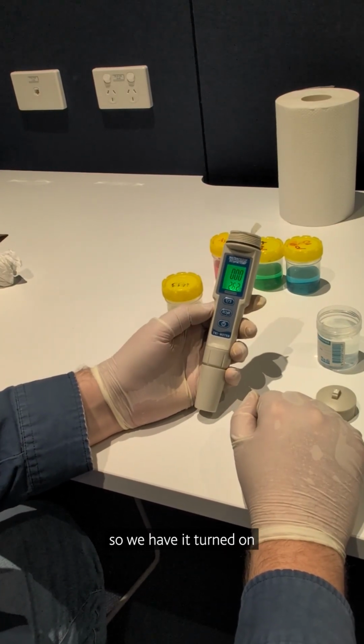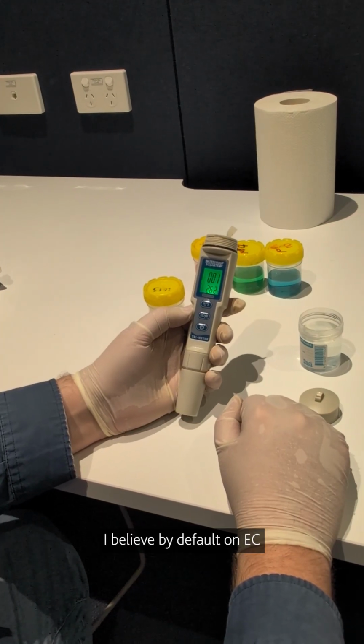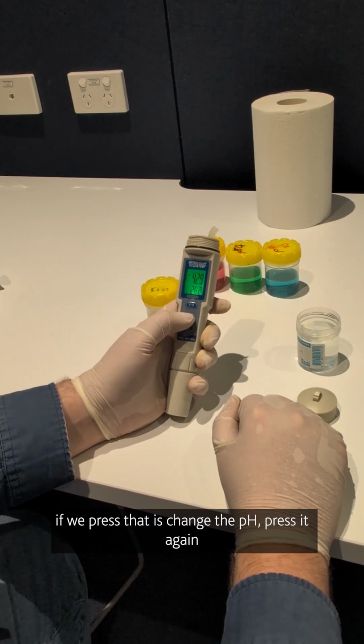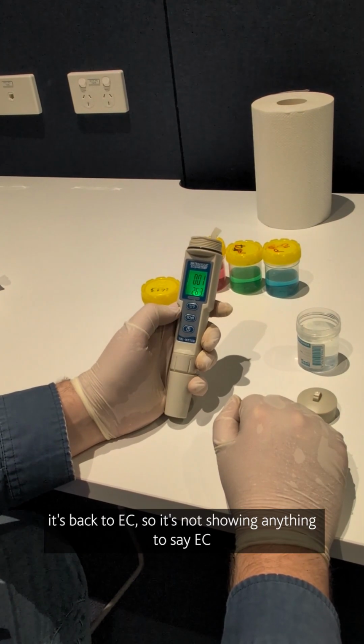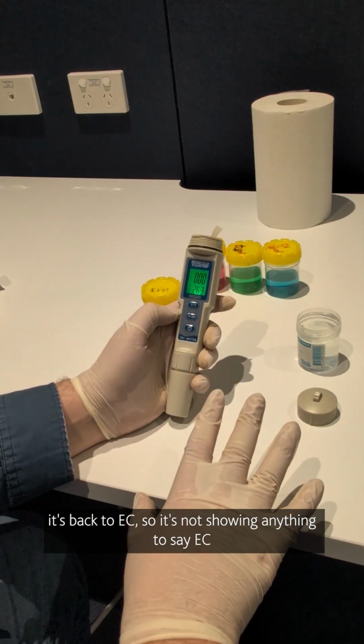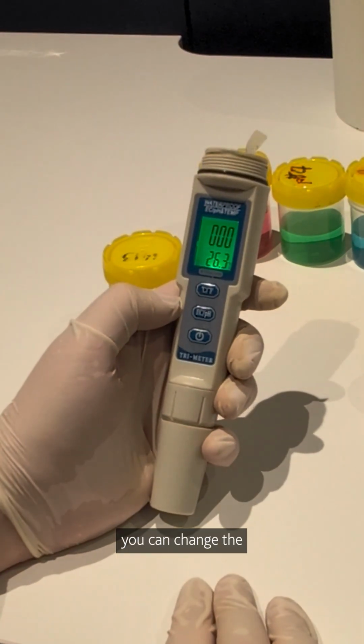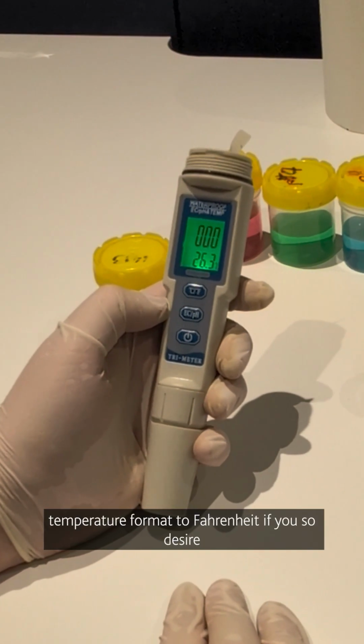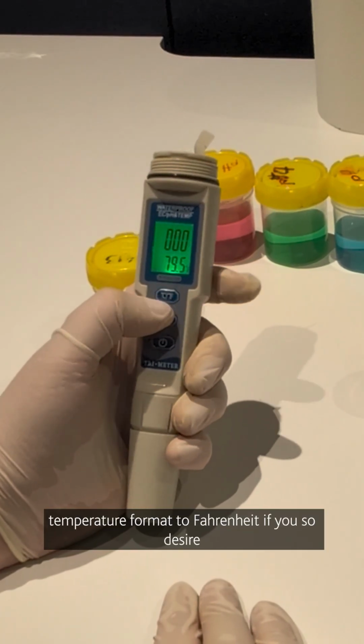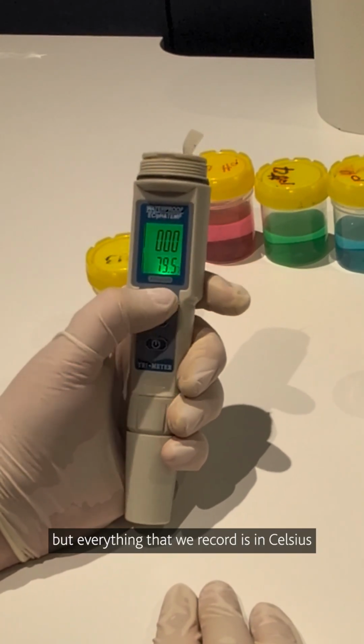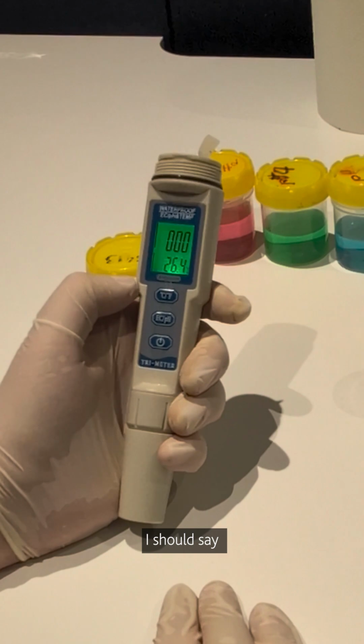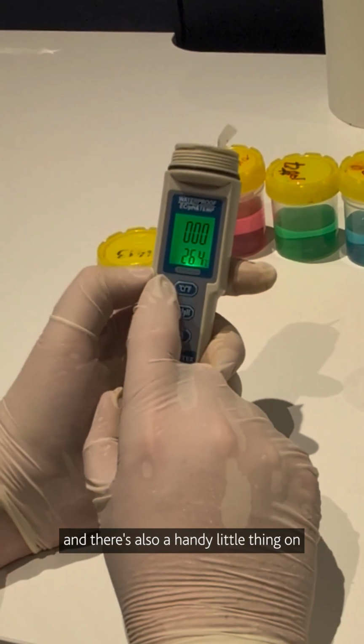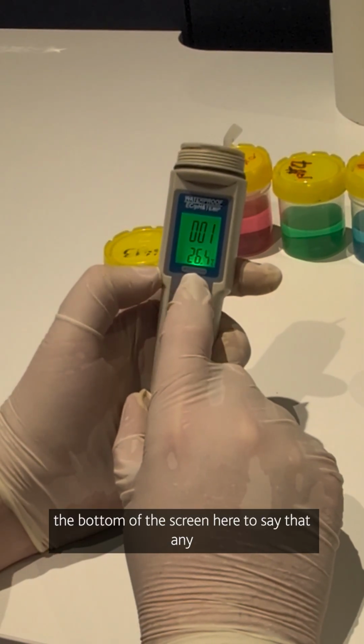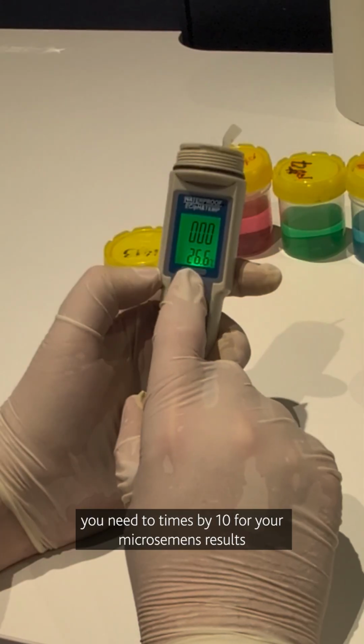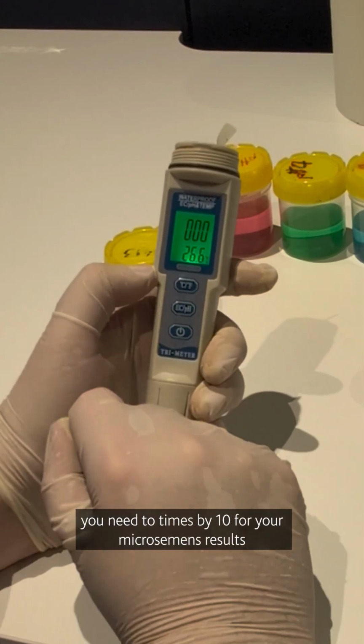So we have it turned on. We're going to make sure that it is, I believe by default it's on EC. If we press that, it's changed to pH. Press it again, it's back to EC. So it's not showing anything to say EC. We can change the temperature format to Fahrenheit if you so desire, but everything that we record is in centigrade, Celsius, I should say. And there's also a handy little thing on the bottom of the screen here to say that any of your results, you need to times by 10 for your microsiemens results.